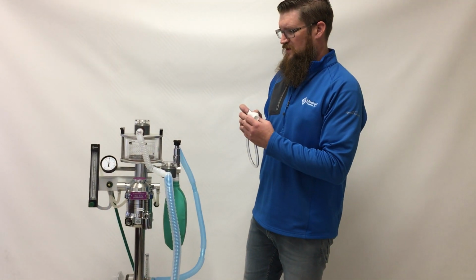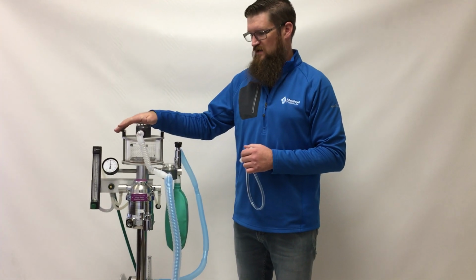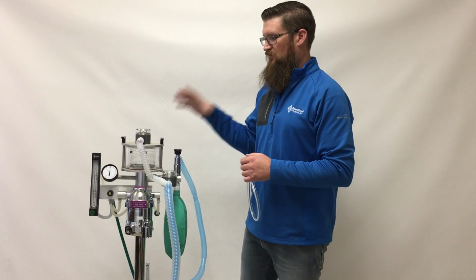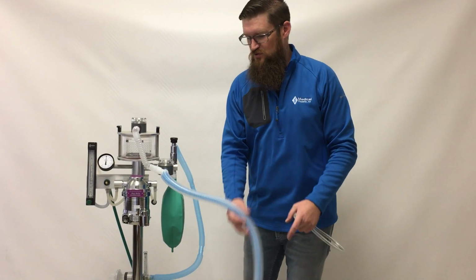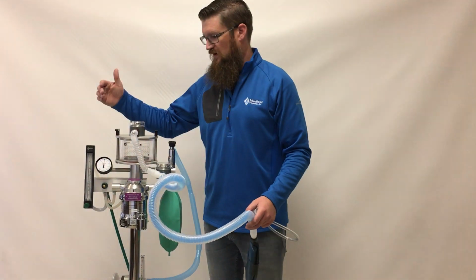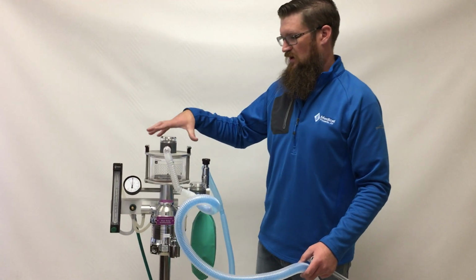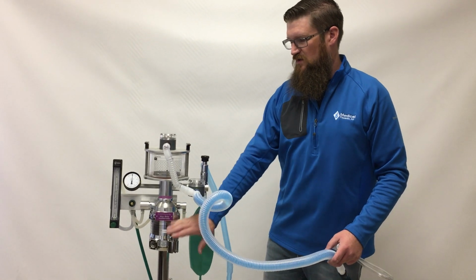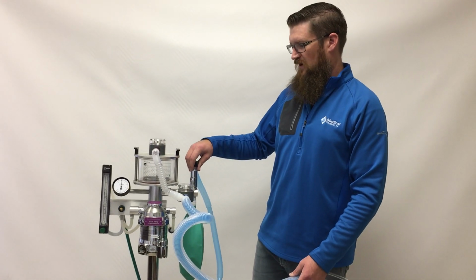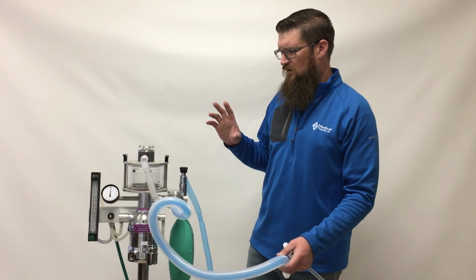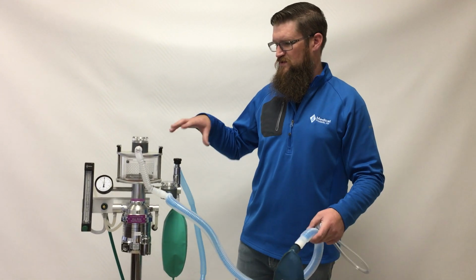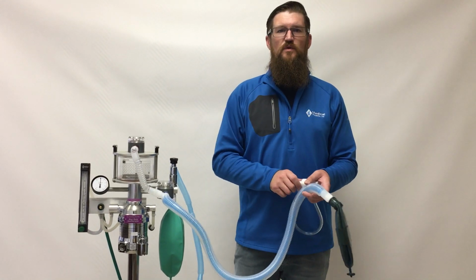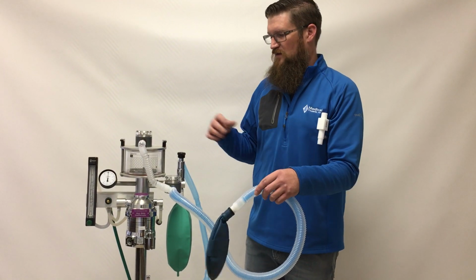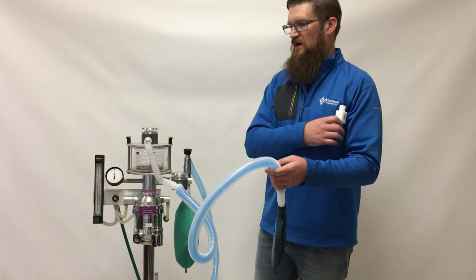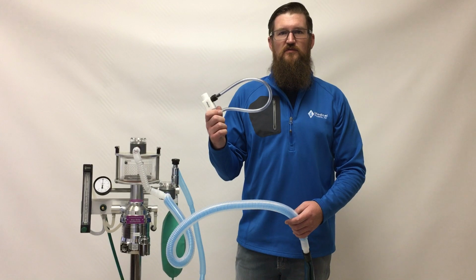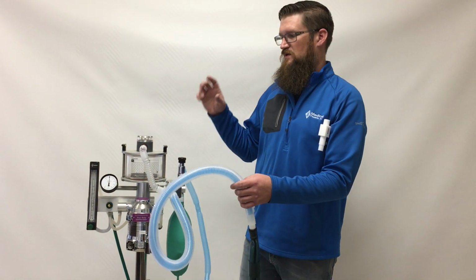The anesthesia machine here we have for demonstration is a JD Medical VT110. Operates the same as any anesthesia machine that you should find in the field. We've got the standard components: flow meter, manometer, circle absorber system with the directional valves, vaporizer, and the pop-off valve. For the demonstration purposes, I'm going to run through the general operation of the anesthesia machine without the safety valve in place, and then we will go through the occlusion valve, and then finally put in the safety valve and see how differently it operates under emergent conditions.